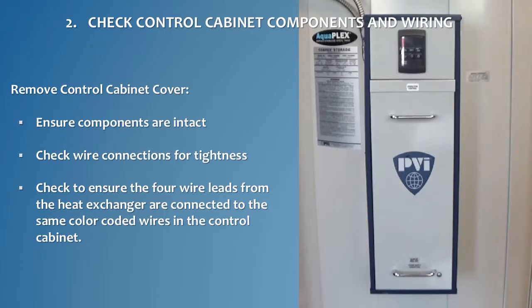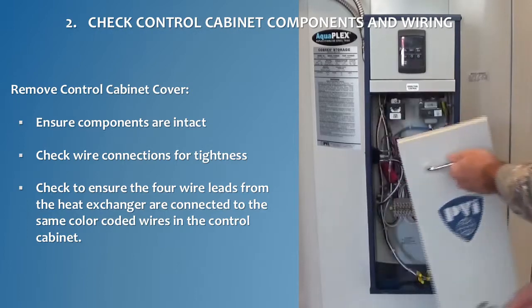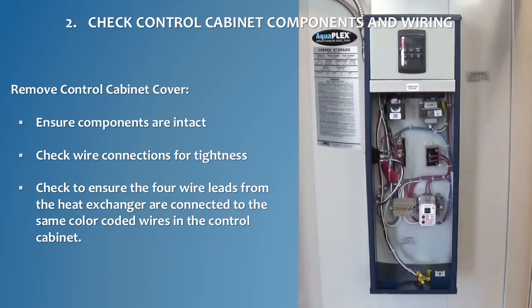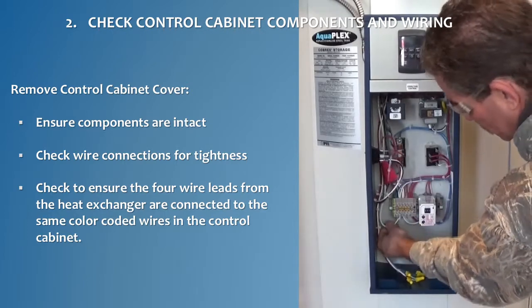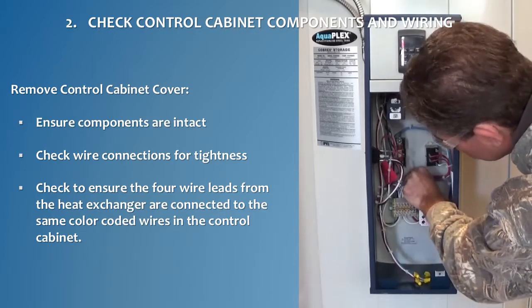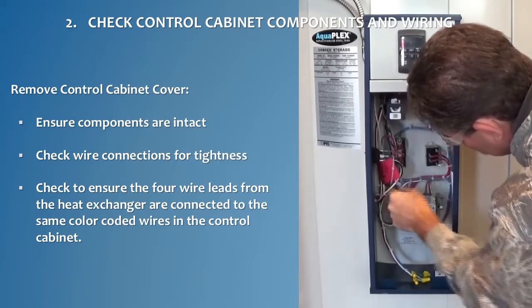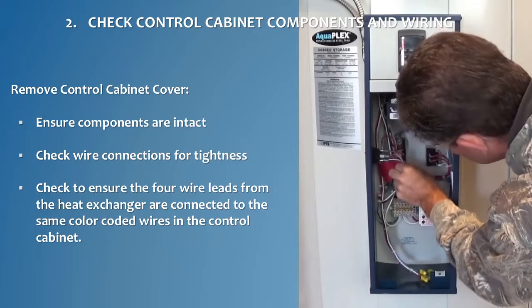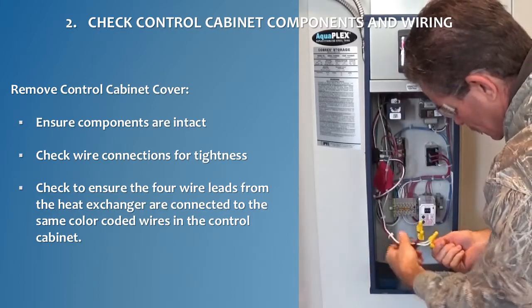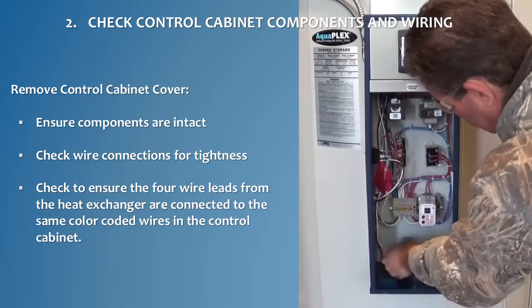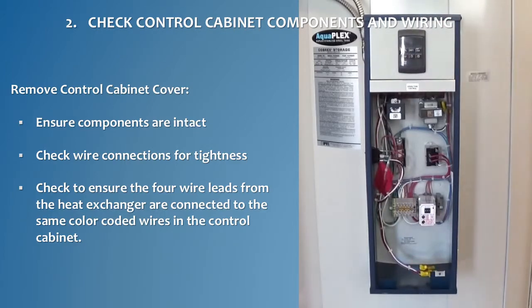Next, remove the control cabinet cover on the storage tank to access the electrical components. Visually check that all components are intact and no damage has occurred during transit or installation. Then check all wiring connections. A loose connection could cause intermittent shutdowns. Check to ensure the wires in the conduit leading from the heat exchanger assembly are connected with wire nuts to the same color-coded wires at the bottom of the control cabinet.